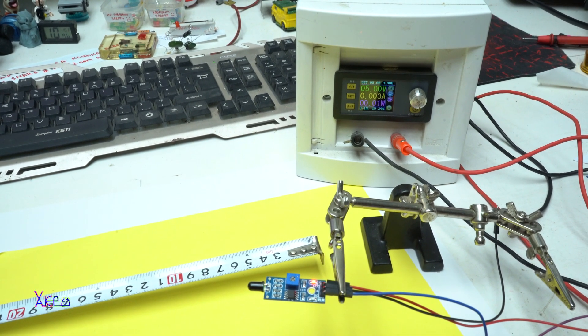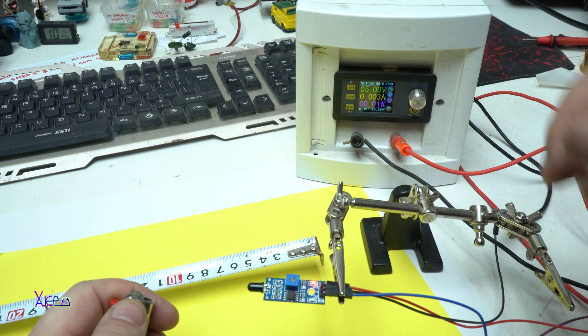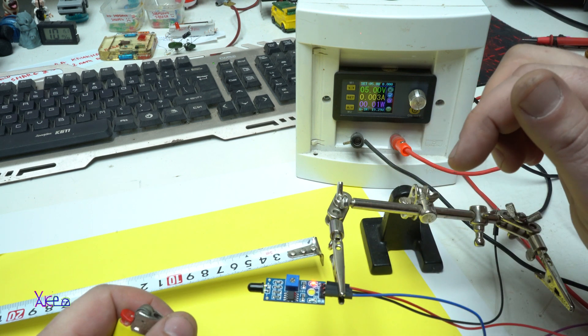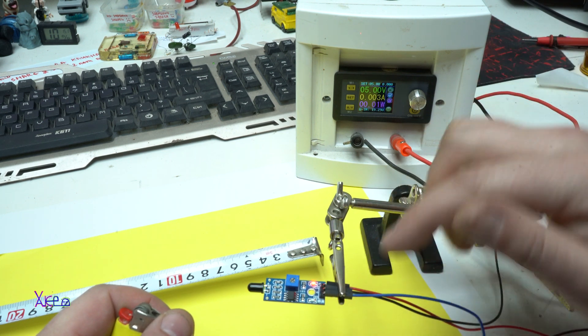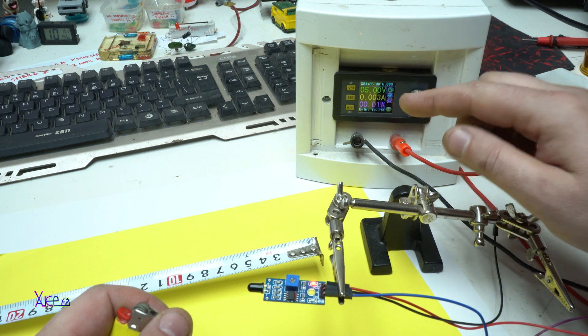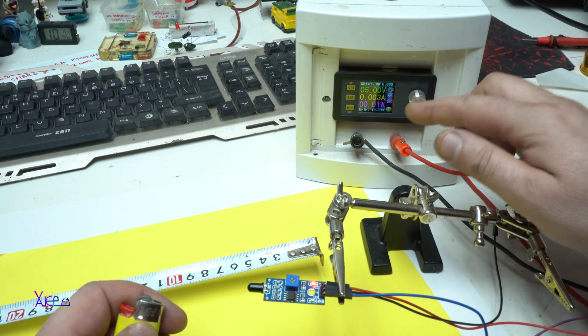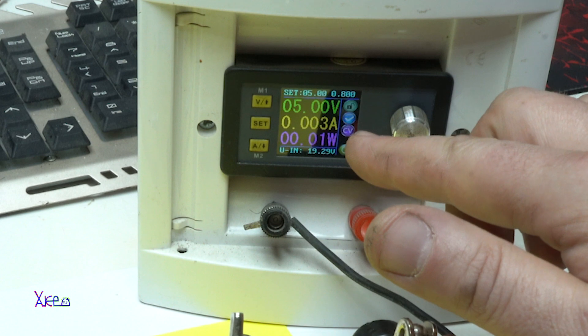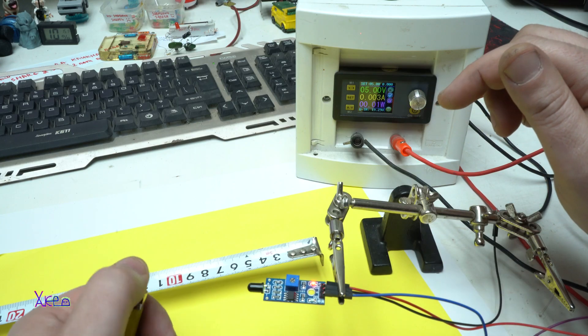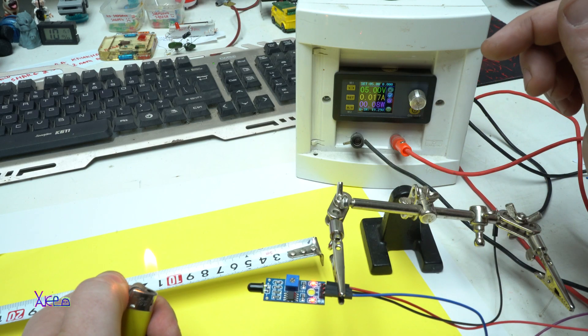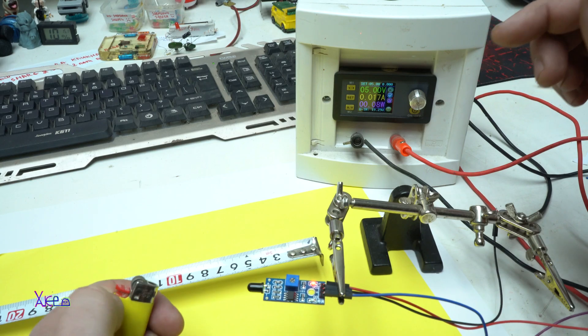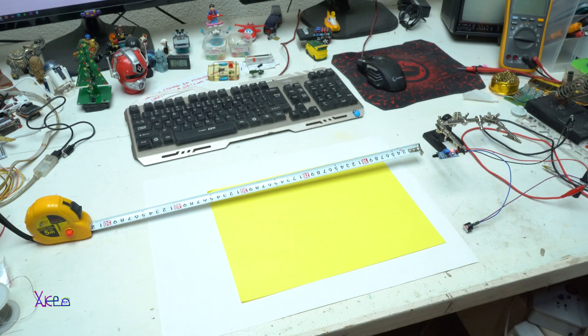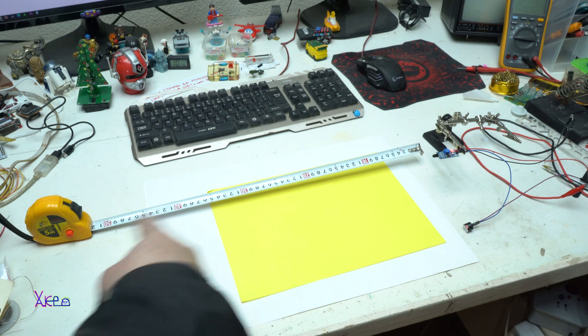Another test is to show you how much current is pulling. The sensor detector model when it's not detecting flame is pulling around 3 milliamps, but when it's active, 17 milliamps.